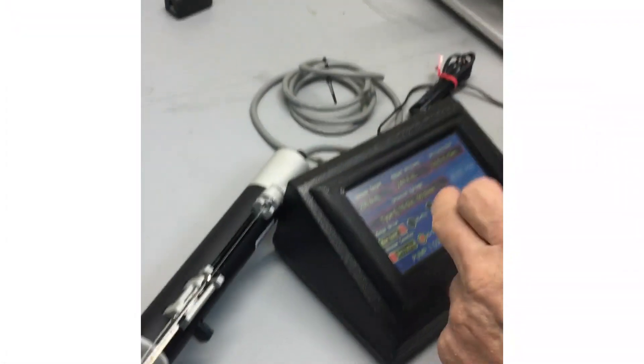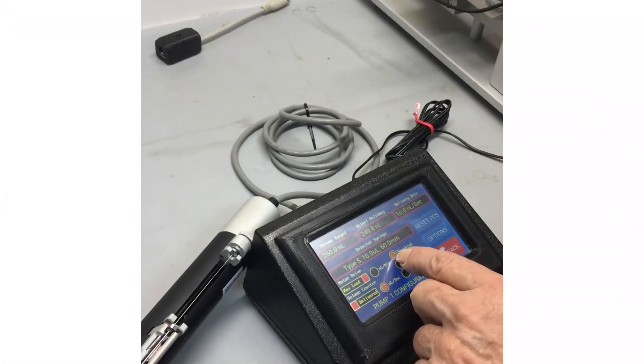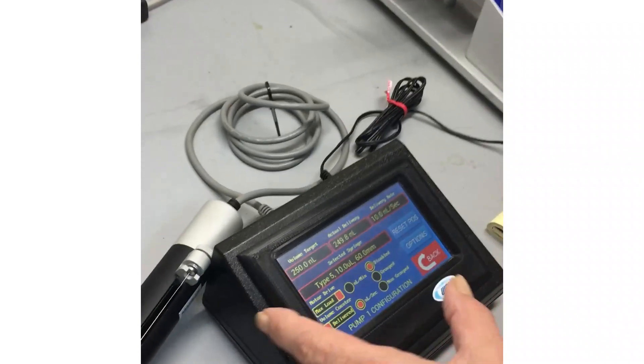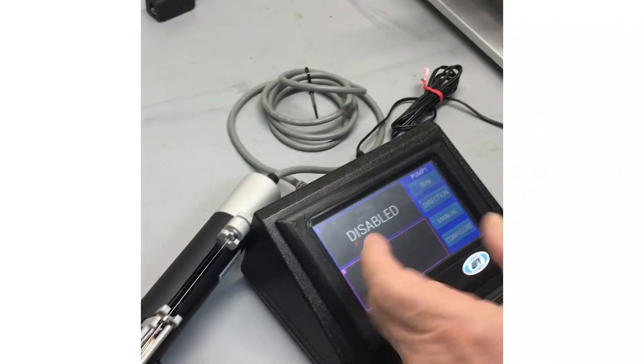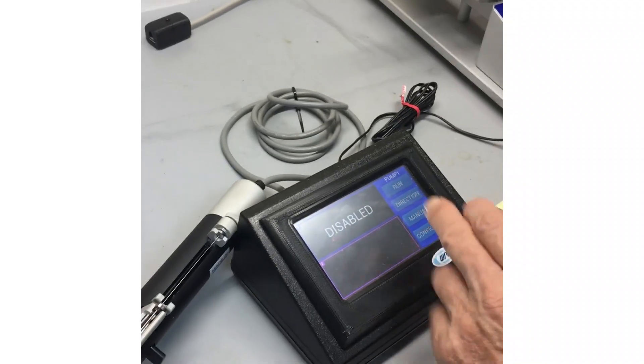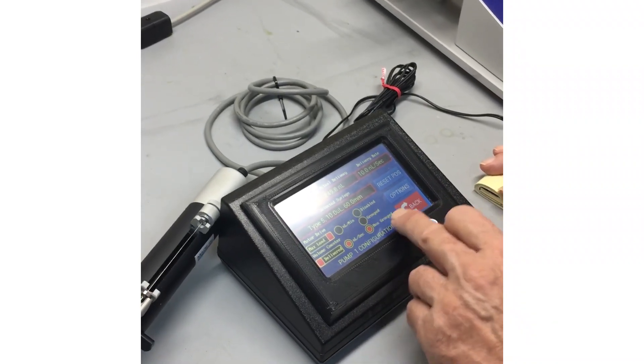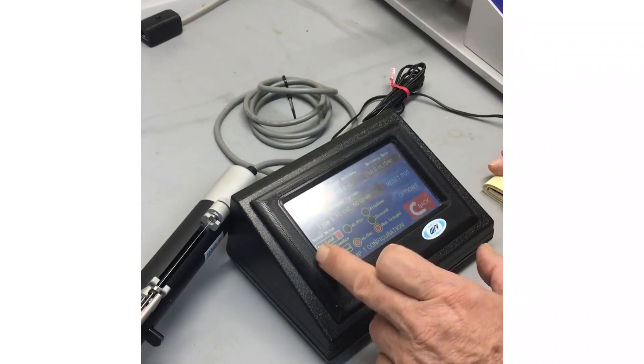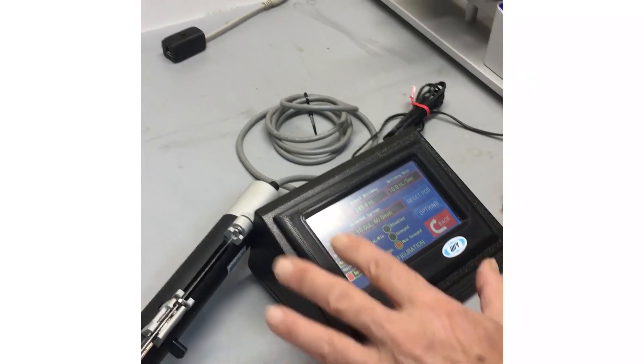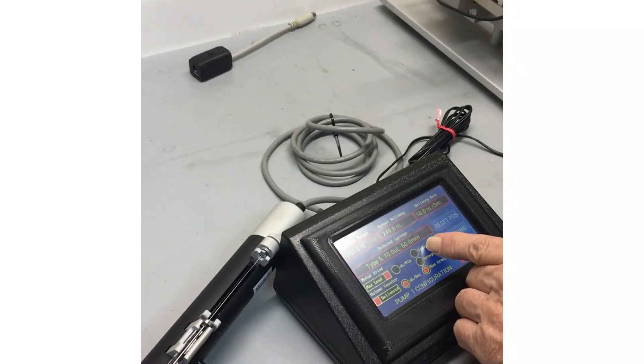Somebody's got rubber gloves on, they press the key, and they hit the disabled button. Now I just disabled pump number one. So if I go back, it says I'm disabled. Believe me, it took us four days to figure out what was wrong here. So you've got to come back in here and choose non-group, then it comes back. But the thing is, they've got to be careful of where they push on here — I want to get rid of this in a new revision.